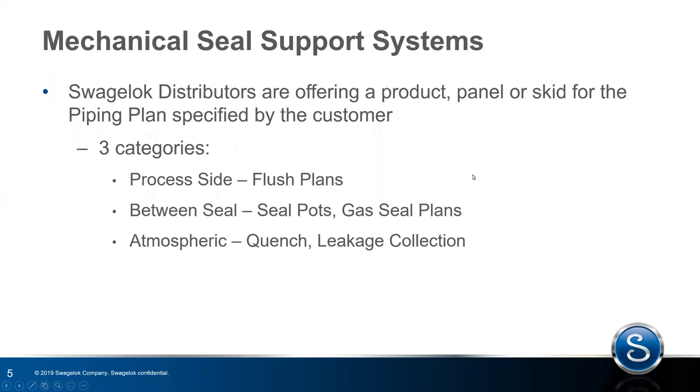To give you an overview of what Swagelok is offering: we'll talk today about specific products to help reduce downtime and improve the operation of seal plans, and the ability for sales and service centers to build panels or entire skid systems for whatever piping plan you specify. In our literature, I've divided out these categories to mirror EagleBurgmann's classification because there's a lot of terminology used in this world. By saying process side, between seal, or atmospheric side, we're highlighting where in relation to the seal face the system goes — process side covers primarily your flush plans, between seal covers seal pots or gas seal plans, and the atmospheric side covers leakage collection and quench.